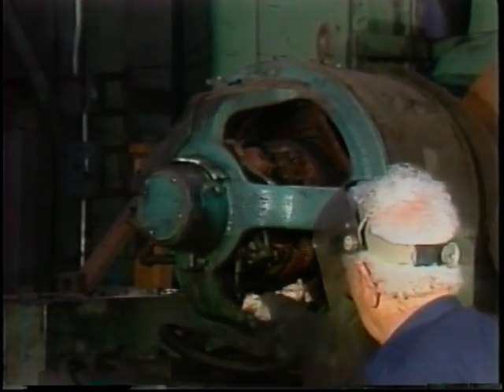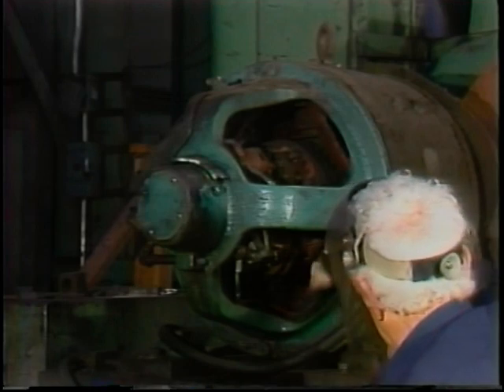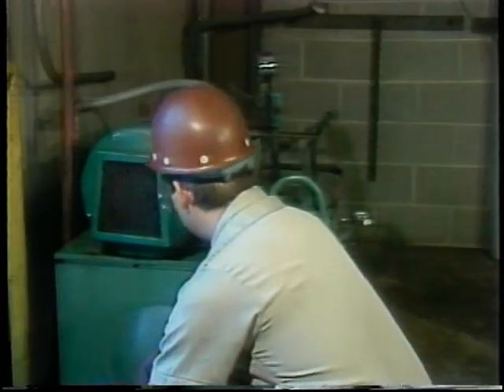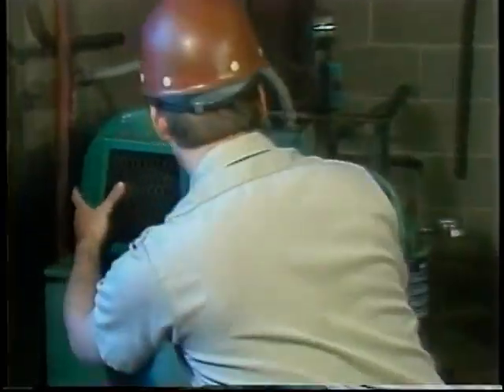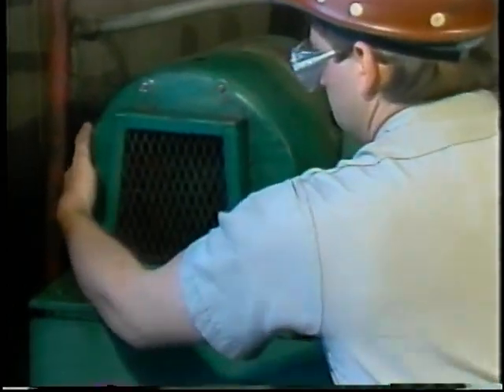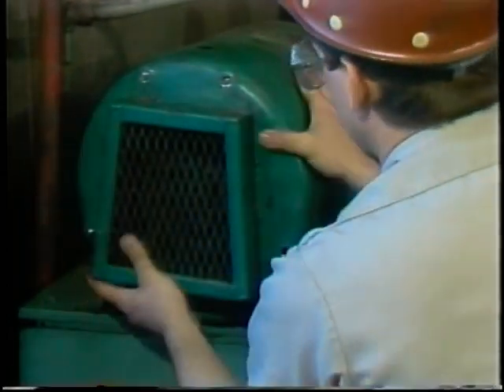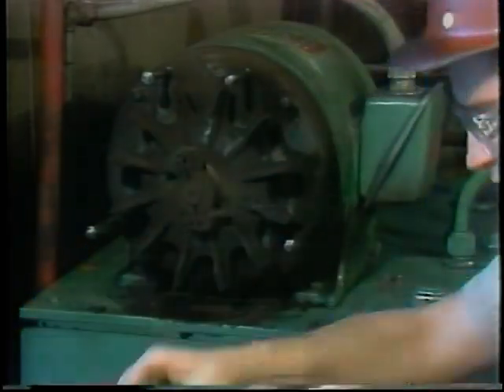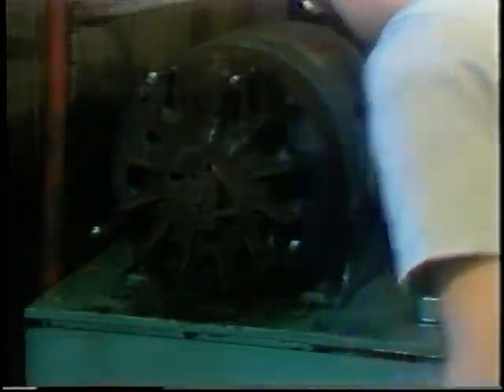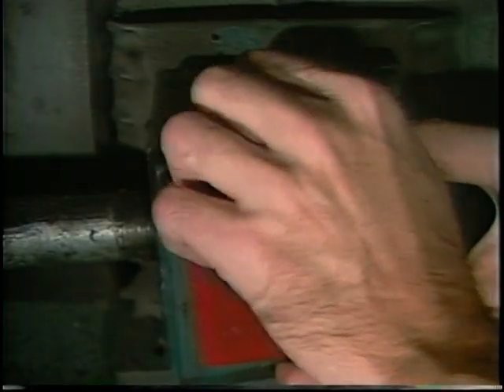Many motors need periodic disassembly for more thorough cleaning and inspection. Even totally enclosed motors may need occasional cleaning out. Be sure power is locked out, and begin by removing the fan shroud on totally enclosed fan-cooled motors. Clean off the fan, the inside of the shroud, and the vents in it for free air flow. Replace the fan if it is damaged. Then inspect the connections in the junction box.